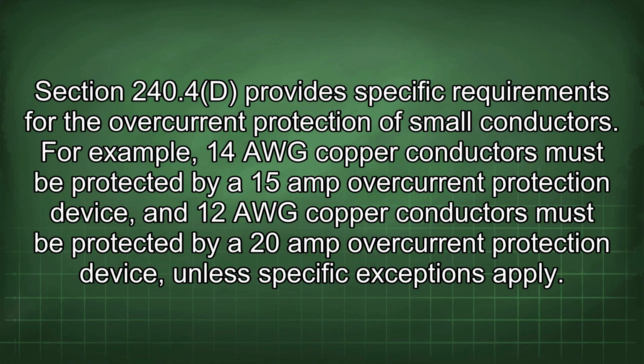Section 240.4(D) provides specific requirements for the overcurrent protection of small conductors. For example, 14 AWG copper conductors must be protected by a 15 amp overcurrent protection device, and 12 AWG copper conductors must be protected by a 20 amp overcurrent protection device, unless specific exceptions apply.